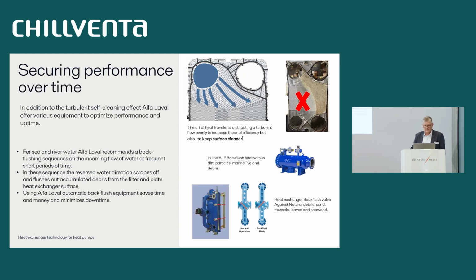If you have fluids that are dirty or fouling, in the plate heat exchanger you have a high turbulent flow, and we get a high wall shear stress, so the units are in fact cleaning themselves. And if we have a good distribution of the fluid over the plate, we can keep the plate normally clean. But if you have very much fouling, sea or river water with dirt and big particles, we would suggest having a backflush filter, a strainer, before. We have those that you can supply, backflush filters that we can wash out the dirt. And if you have a marine environment with shells and so on, also a backflushing valve. These also backflush the plate heat exchanger itself. So these are available for such duties.